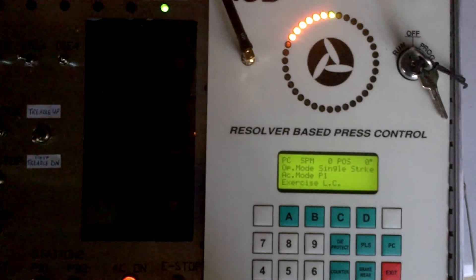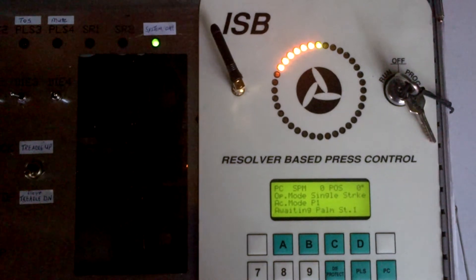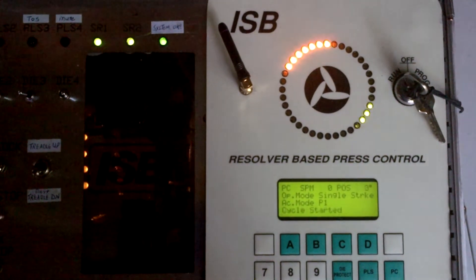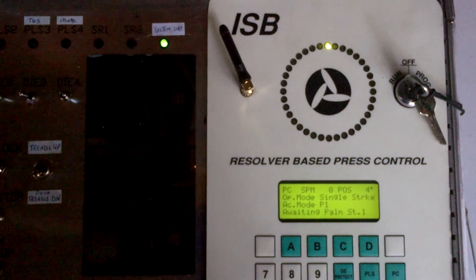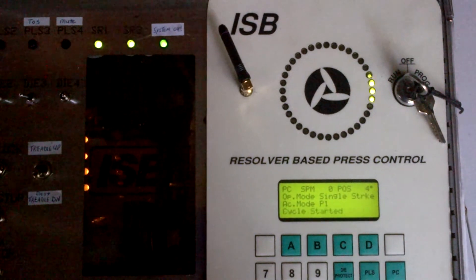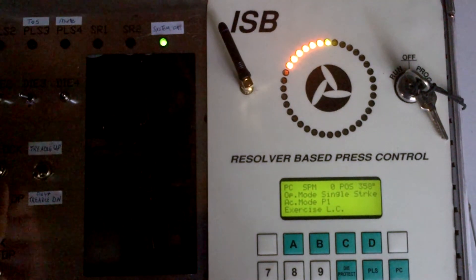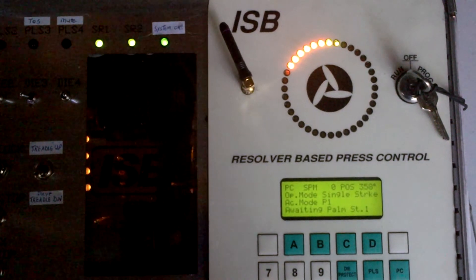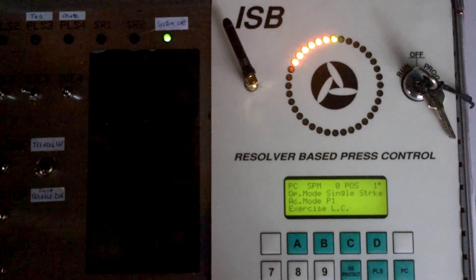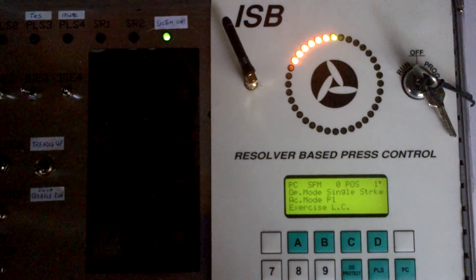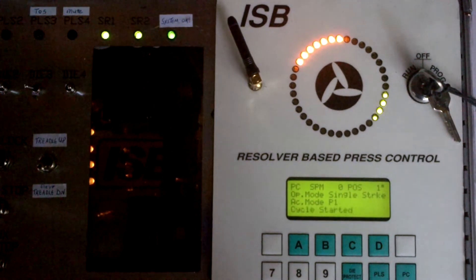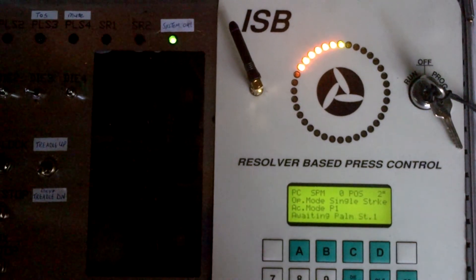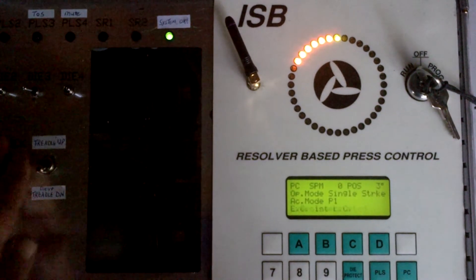and follow the prompts, exercise light curtain, press the pound buttons in. And in this case you'll see that the unit's already at zero or 358 degrees. The first stroke could be anywhere in the rotation. You need to continue to make a bunch of strokes in the single stroke mode.